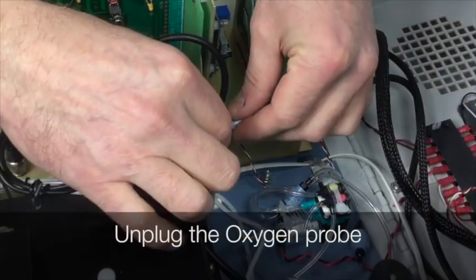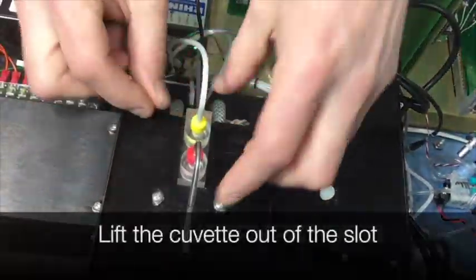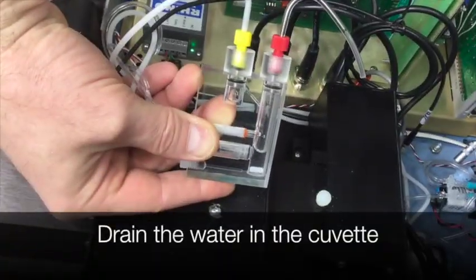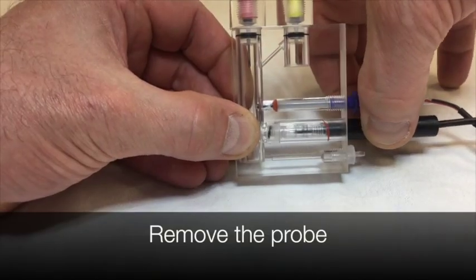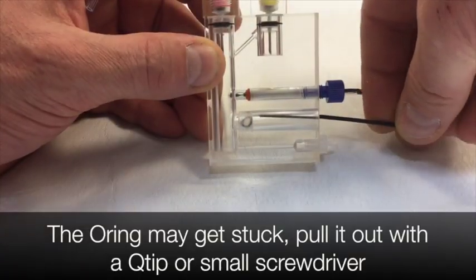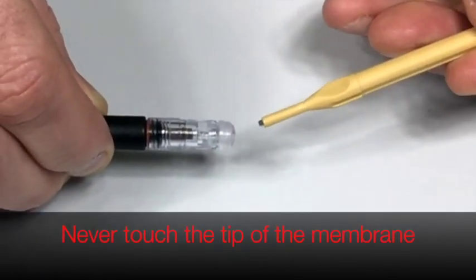Open lid. First, unplug the oxygen probe. Lift the cuvette out of the slot. Drain the water in the cuvette. Remove the probe. The O-ring may get stuck. Pull it out with a Q-tip or a small screwdriver. Never touch the tip of the membrane.